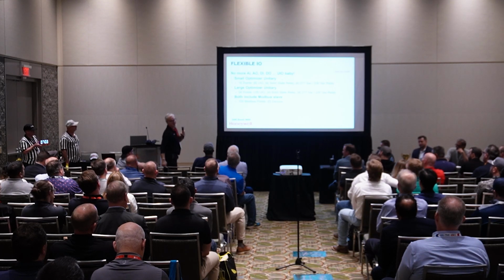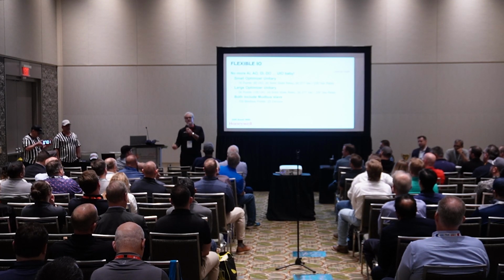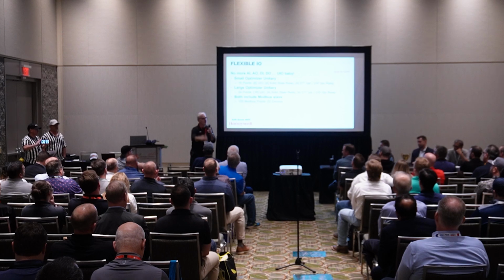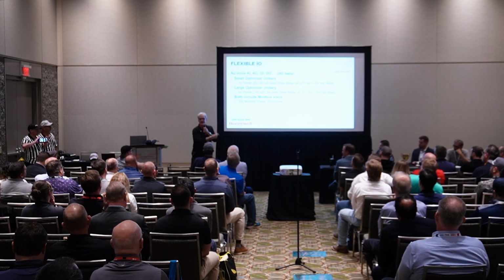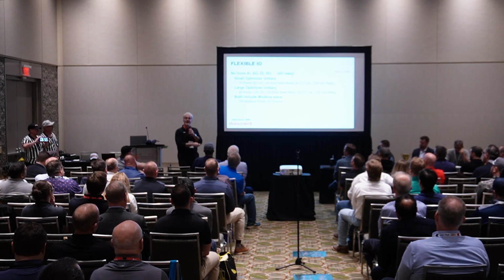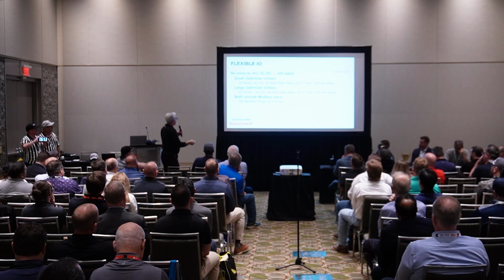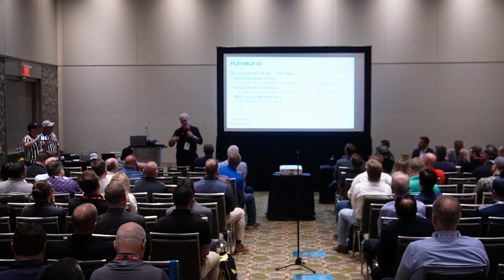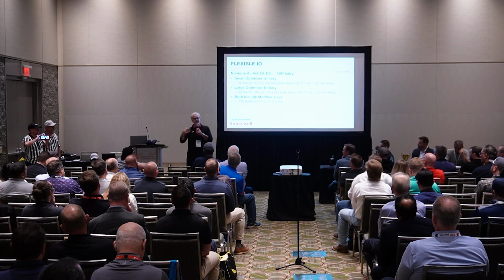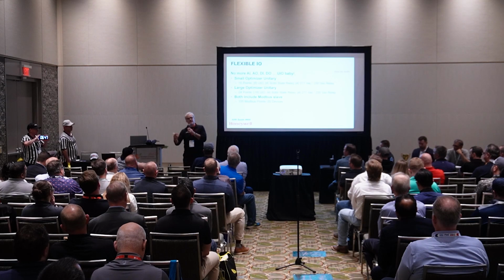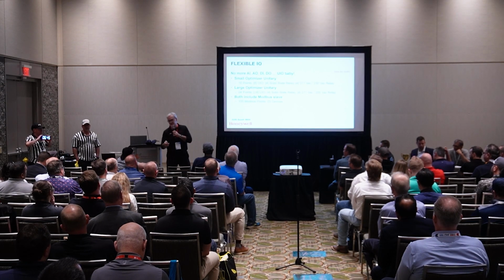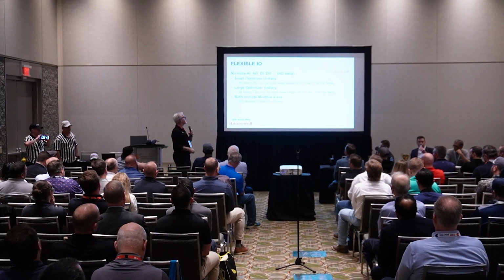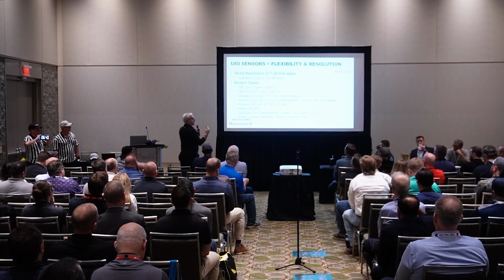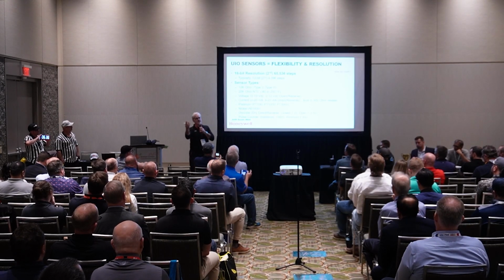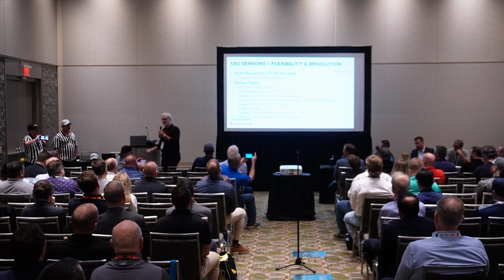So the small one has 16 points: 8 universal I/Os, 4 solid state relays, 4 high voltage relays. The large one has 24. We also have a Modbus port on the device. So if I need to add points today, I can do up to 5 devices, 155 points off that Modbus sub-bus if I need expansion. This to me is a pretty big deal. Hopefully it makes sense to y'all.